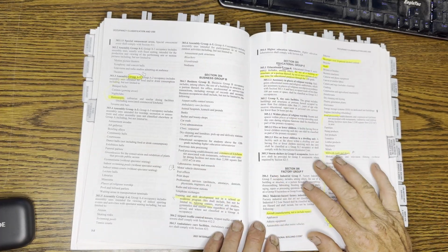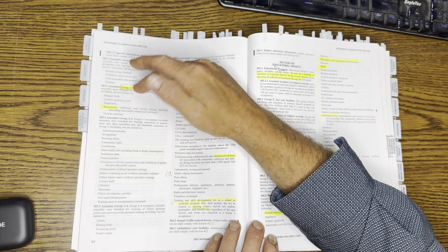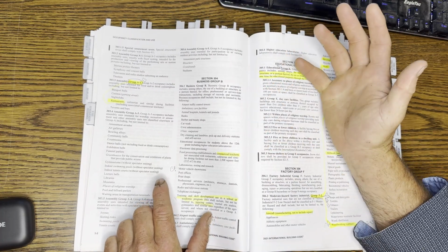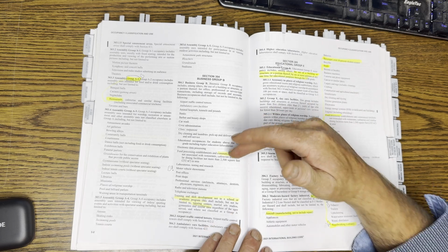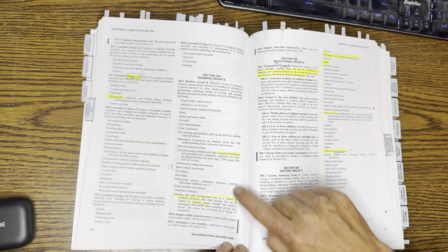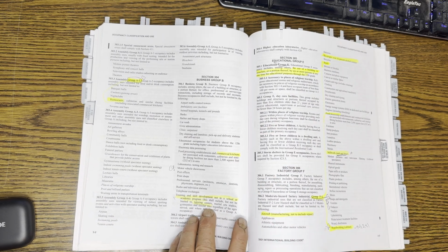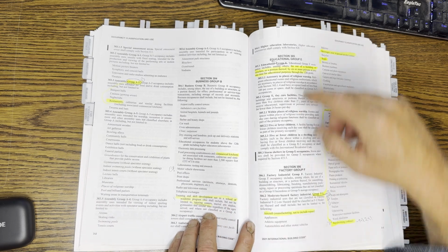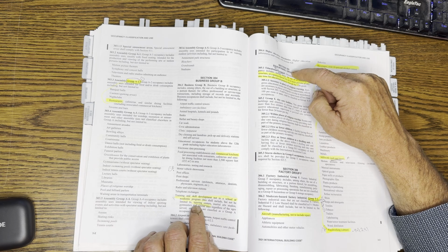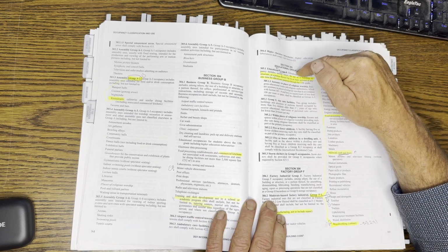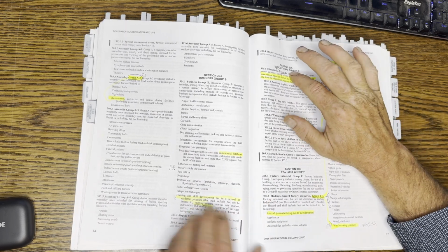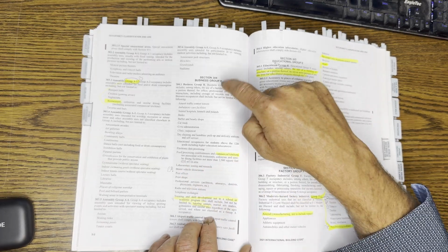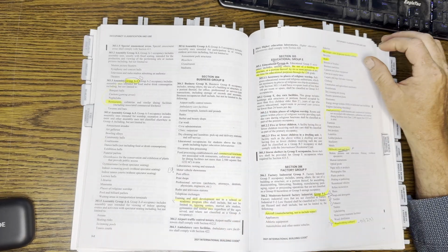Chapter 3 goes through occupancy definitions, but know that A2 is a restaurant. Know that, you have all these sections like commercial kitchens, training. I want to be clear, when it says training, that is not K through 12. And Group E is not training necessarily. Group E is specifically K through 12. So they delineate this very clearly. If you go to a college or community college, that's a Group B occupancy. It is not a Group E. So don't get thrown by that.